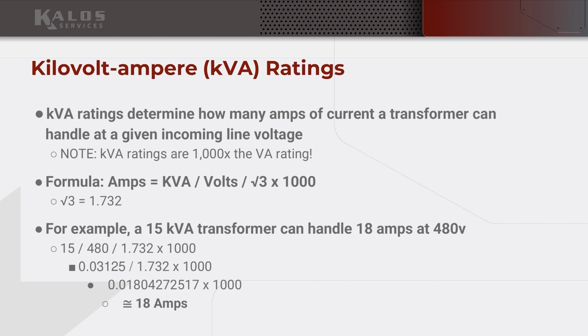Kilovolt ampere ratings, kVA ratings. Smaller transformers will be measured in VA. So K just means 1,000. So if we have a 45 kVA transformer, that means that transformer is capable of delivering 45,000 watts of power. A kVA rating determines how many amps of current a transformer can handle at a given incoming line voltage.